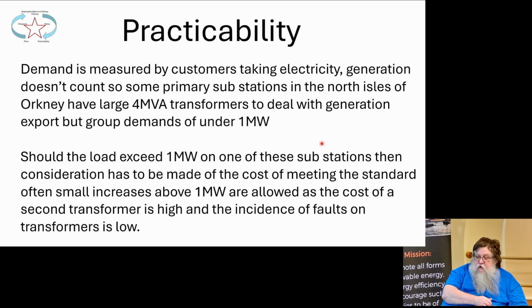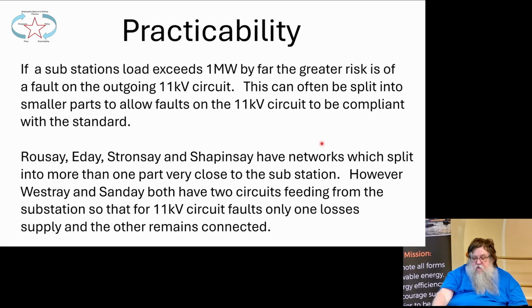Should the load exceed 1 megawatt on these substations, then consideration is to be made to the cost of meeting the standard. Often small increases above 1 megawatt are allowed as the cost of a second transformer is high and the incidence of faults on transformers is low. If a substation load exceeds 1 megawatt, by far the greater risk is of a fault on the outgoing 11 kV circuit.